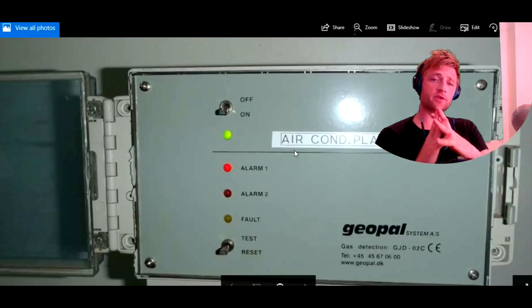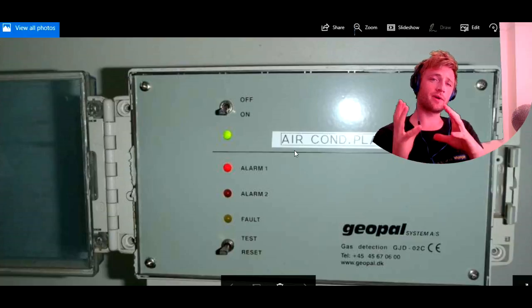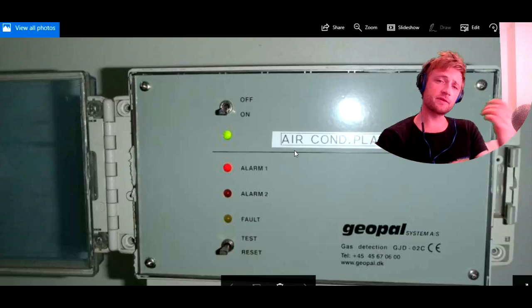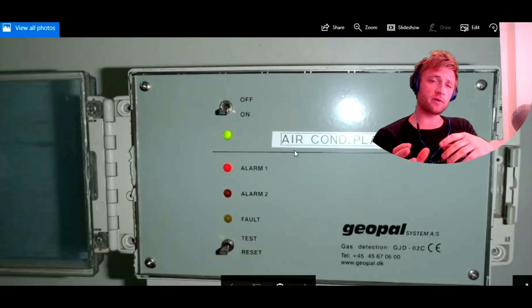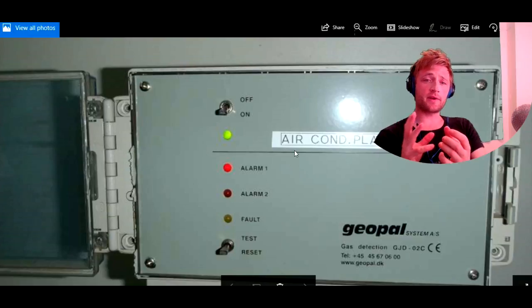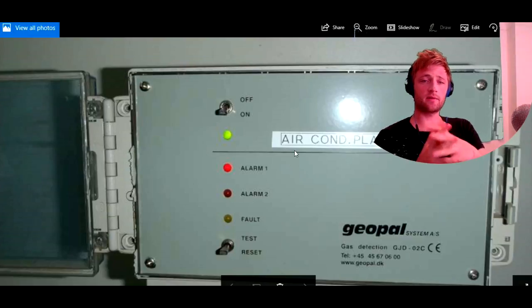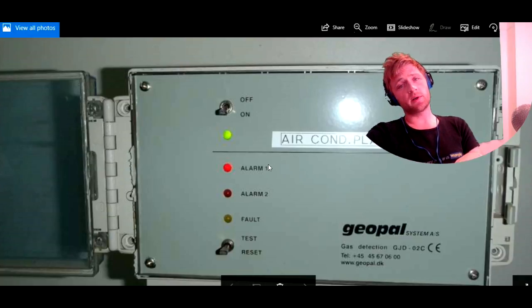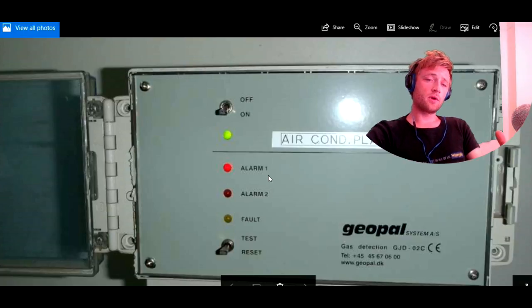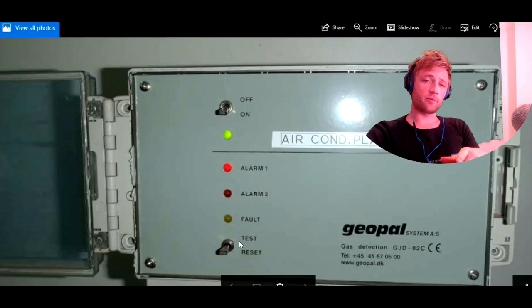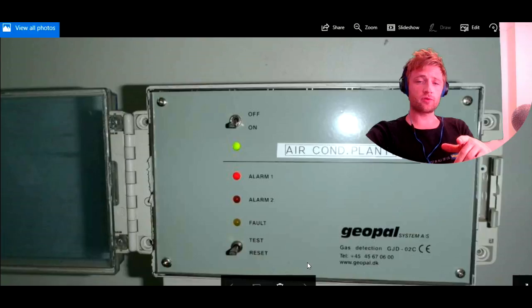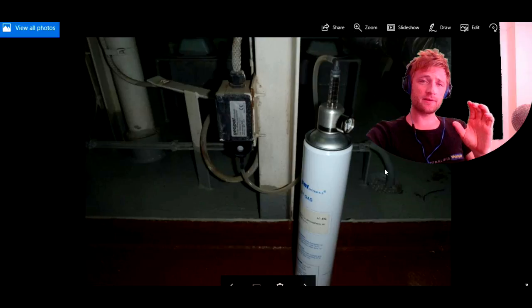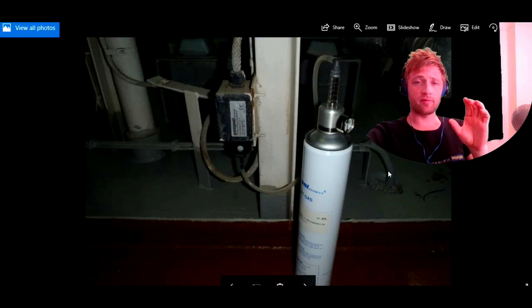This is why we have two alarms, because we have two air condition plants in engine room. And if any leakages occur due to some crack or something—we don't know—some safety valve open, some part is broken, immediately if this sensor detects the gas, this will trigger an alarm. And this alarm also will be seen in this panel and down in the engine control room. So you can test from local here, this alarm. You can reset also from this panel. And next we move on to next picture to see how the test is being performed.